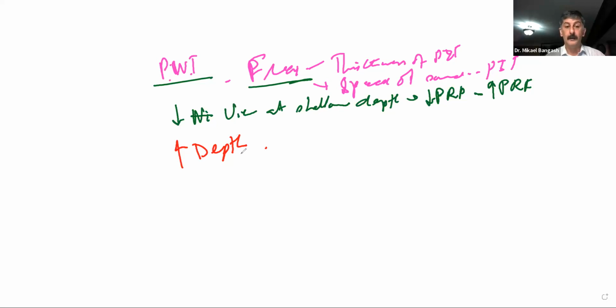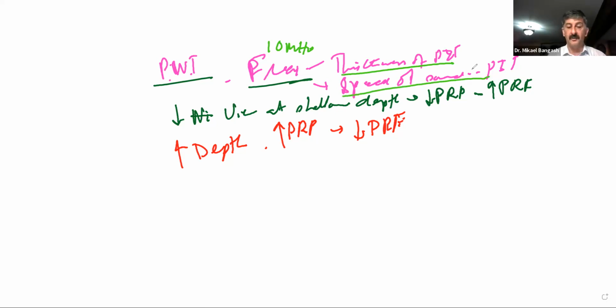So when you increase the depth of your image, the pulse repetition period will increase, which will lead to a decrease in the pulse repetition frequency. But the frequency of this transducer is still, let's say, 10 megahertz. What determines that it has a frequency of 10 megahertz? That is determined by the thickness of the PZT and the speed at which the sound travels through that PZT.